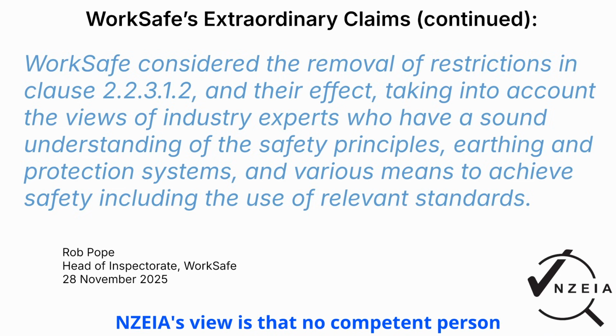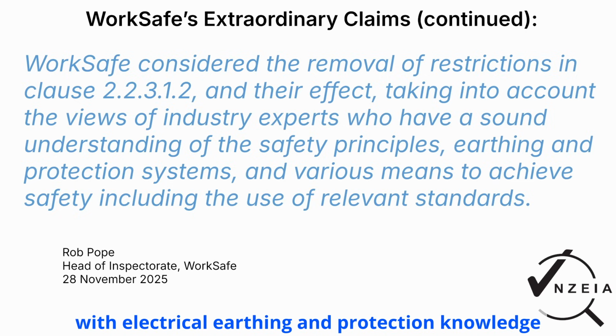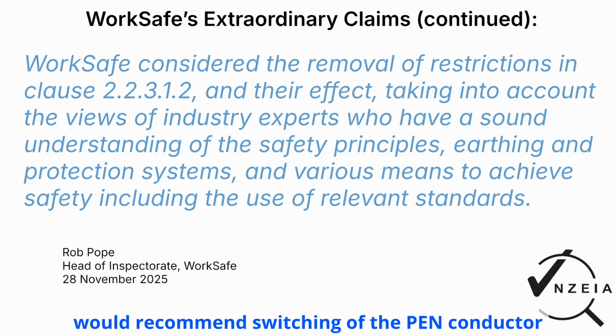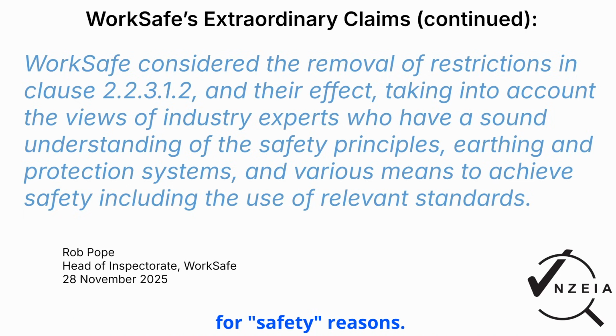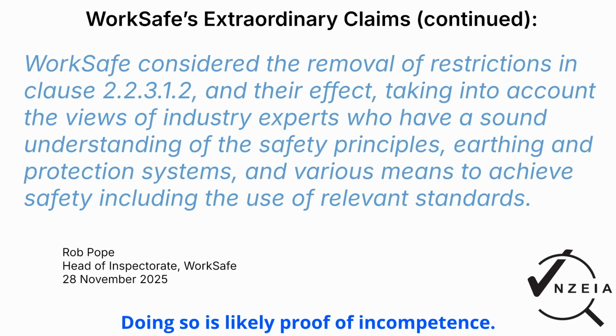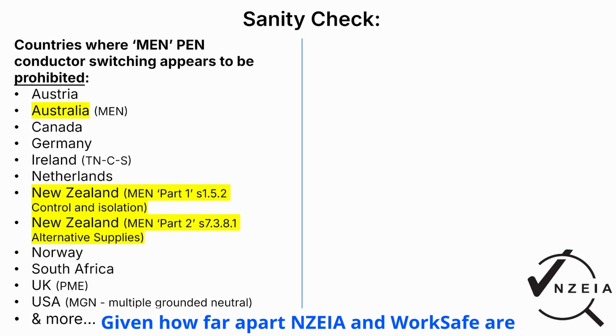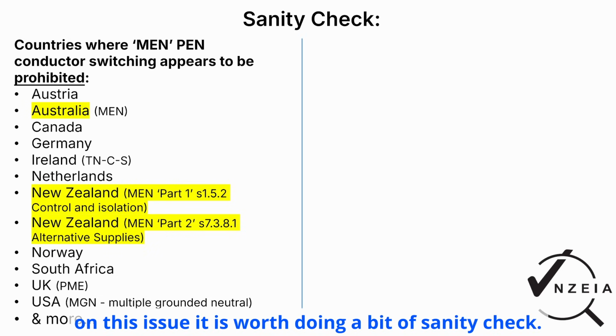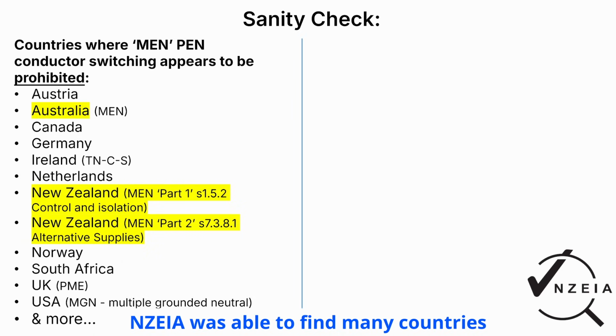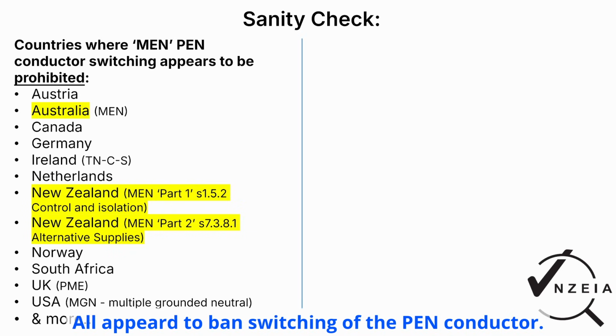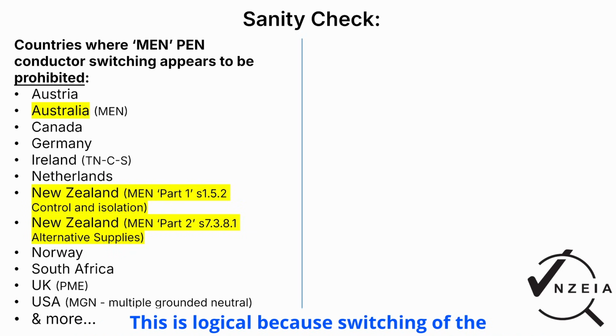NZEIA's view is that no competent person with electrical earthing and protection knowledge would recommend switching of the PEN conductor for safety reasons. Doing so is likely proof of incompetence. Given how far apart NZEIA and WorkSafe are on this issue, it's worth doing a bit of a sanity check. NZEIA was able to find many countries with MEN-style systems of supply. All appeared to ban switching of the PEN conductor. This is logical because switching of the PEN conductor is demonstrably unsafe.